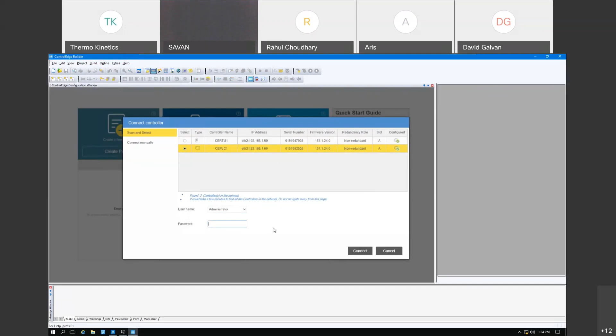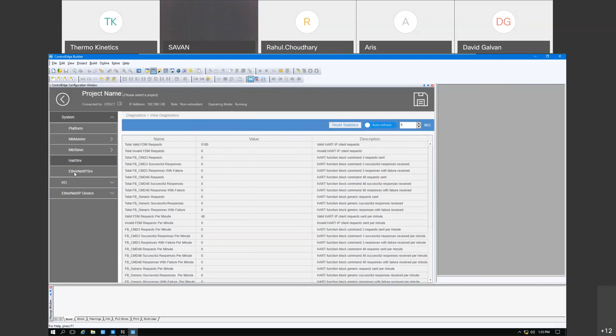Okay, let's open a project. Well, before I open a project, I want to show you what you can do even without a project open. Without a project open, just connected, I can view diagnostics of the PLC. Right off the bat, you get all your PLC diagnostics and statuses. You get CPU utilization, serial number, temperatures, CPM temperatures, all this cool stuff. Enclosure temp, network statuses, you name it. Here are your Modbus master diagnostics, any HART slave, EIP, and your IO rack. So you get your IO rack diagnostics here off the bat. Everything's okay. It gives you firmware rev.